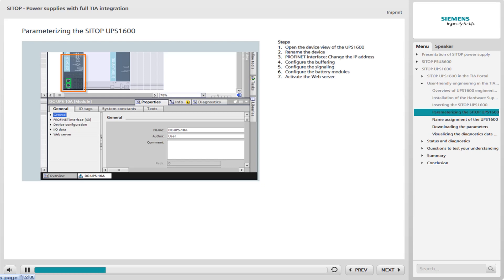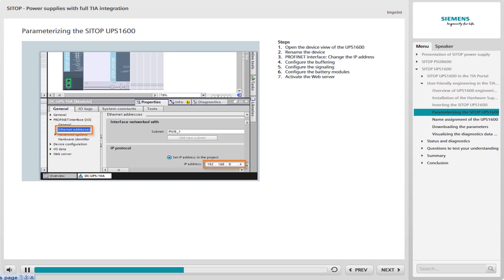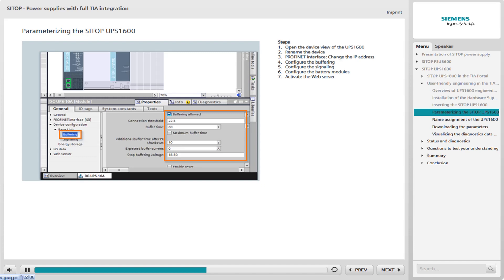In the first step, select the UPS 1600 by clicking on the graphic in the editor. To change the name of the device, select the Properties tab in the Device Data area and then select General in the General area. Assign the name of the UPS 1600 in the relevant field. The name DCUPS10A used in the example is also used as the PROFINET device name. For the PROFINET interface, you can adapt the IP address of the device accordingly in the Ethernet address area.